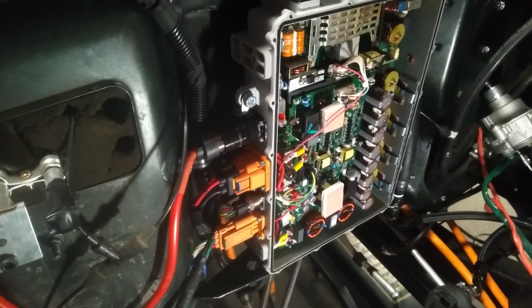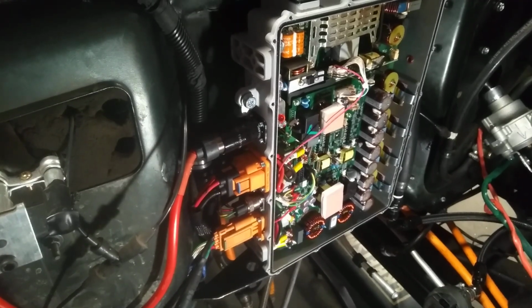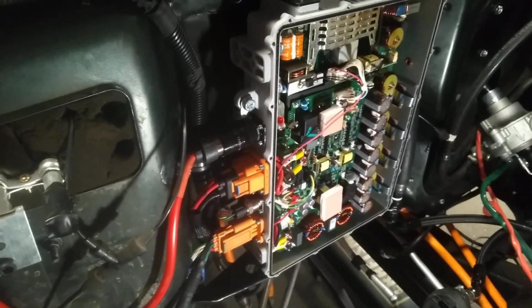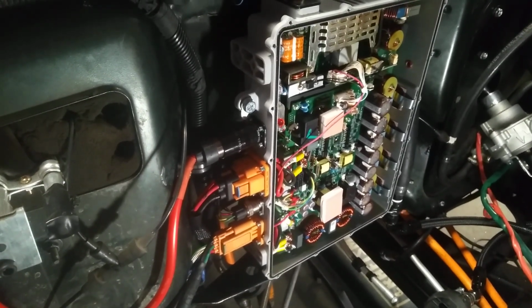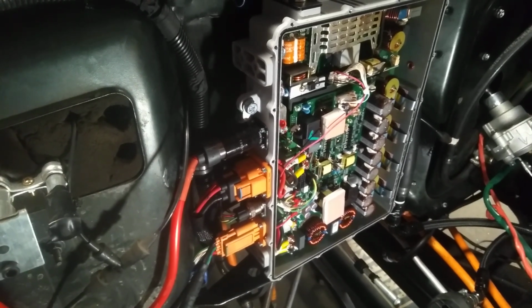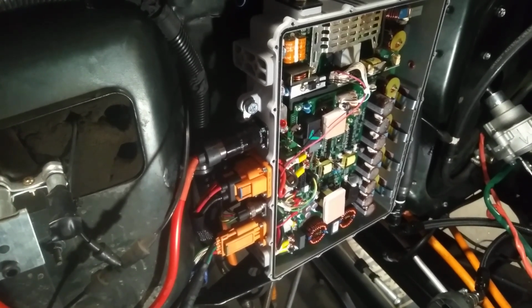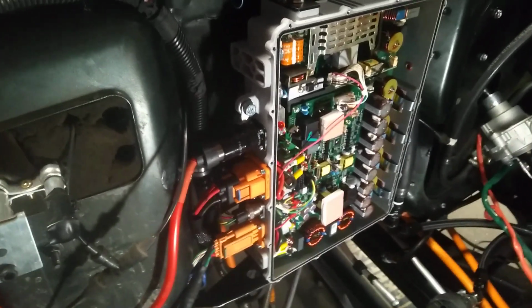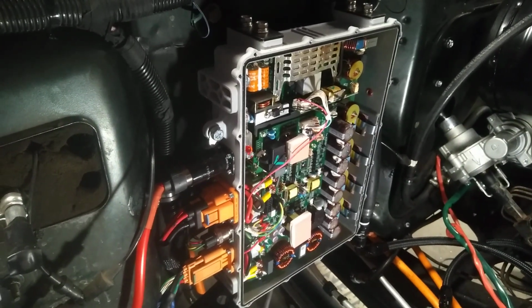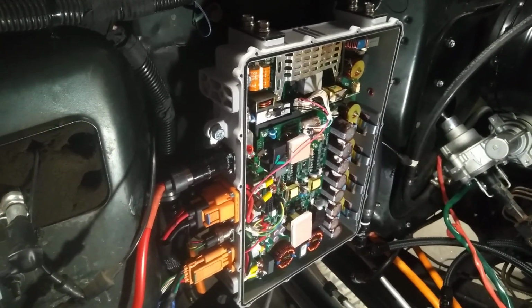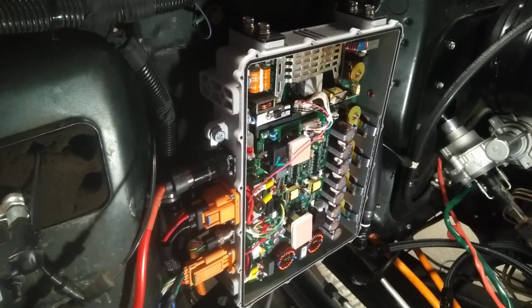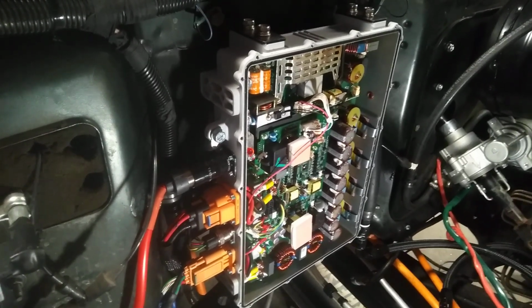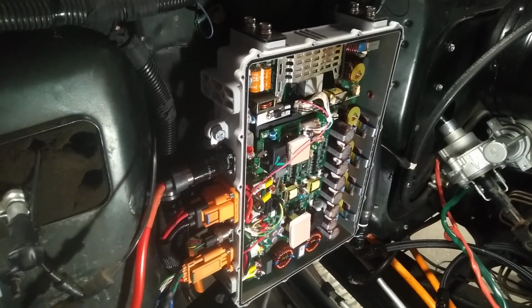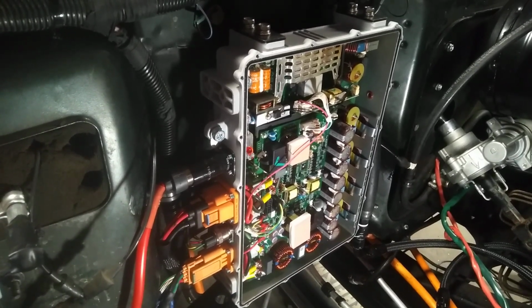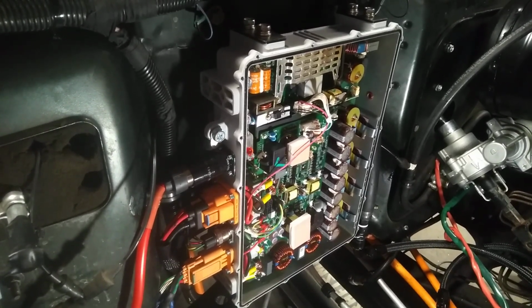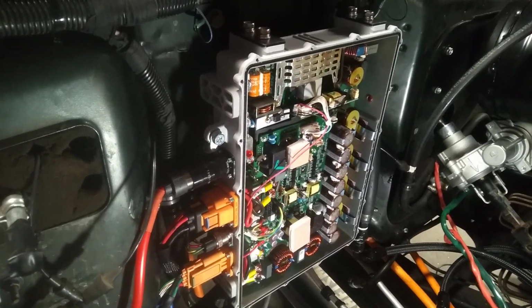And if, for some reason, the negative contactor you installed was faulty, and it just welded itself shut, or maybe it was welded shut from the factory, you don't know. How would you know if the negative contactor was bad? If you've got a positive contactor that's essentially killing your high voltage circuit, your negative contactor is just sort of a backup to that. But if the backup was faulty, you'd never have a way of knowing.